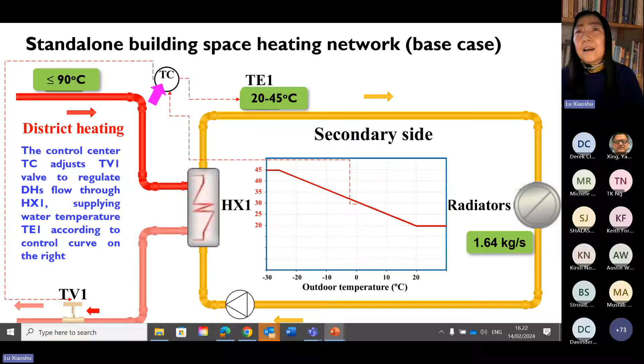And this is our invention, scheme 1, that recovers waste heat on the secondary side. It can achieve 100% waste heat recovery. The lower section represents the direct-to-chip cooling system, and the upper section represents building space heating. The middle square represents our proposed heat exchanger that recovers waste heat from the secondary side of the CDU to serve the space heating at temperature TE1, according to the regulated control curve that I showed in the previous slide, which is based on the Finnish regulation.